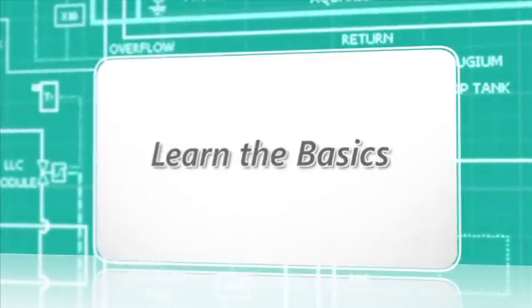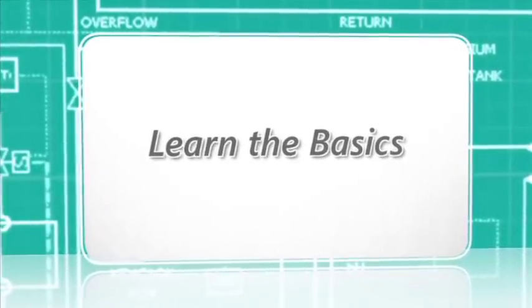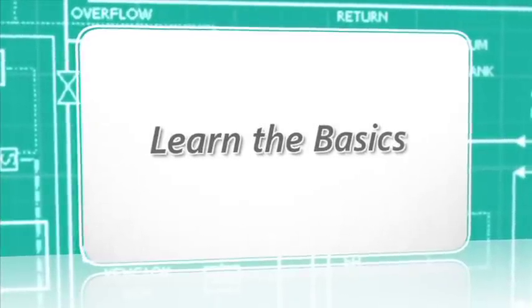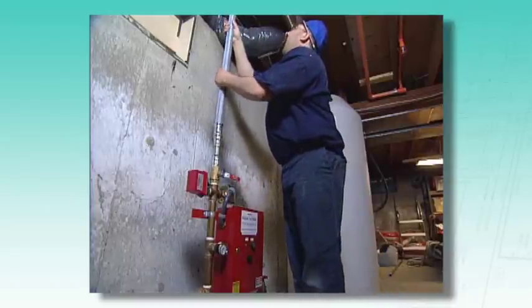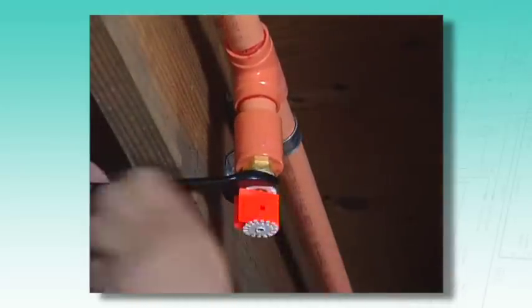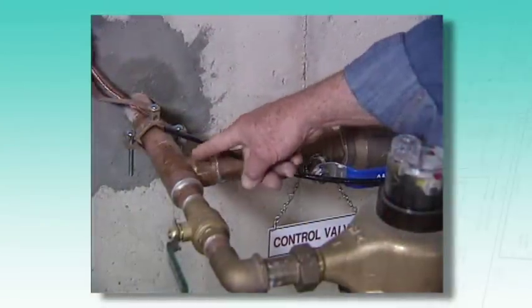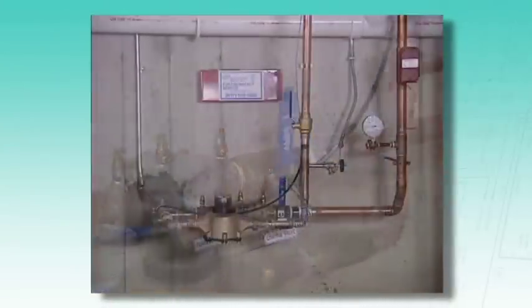In the next few minutes, you'll learn the basics of residential fire sprinkler systems, their water usage, and other important information. Water utilities are familiar with traditional commercial and industrial fire connections, which are always a separate and distinct pipe from the domestic water supply to a building. The NFPA 13D fire standard allows designers to utilize just a single line that supplies both fire and domestic flow.